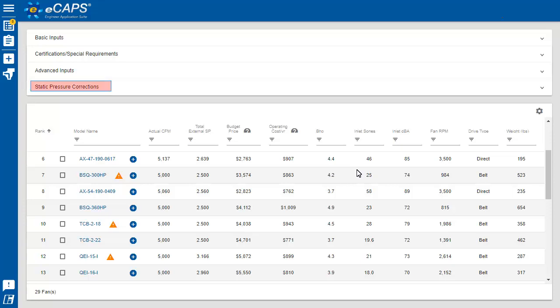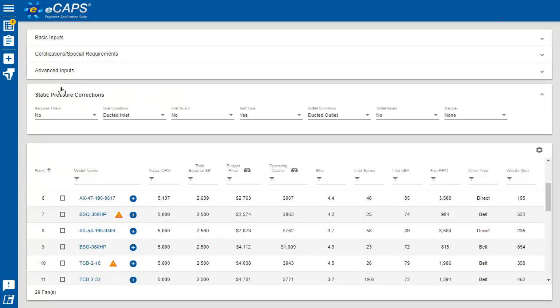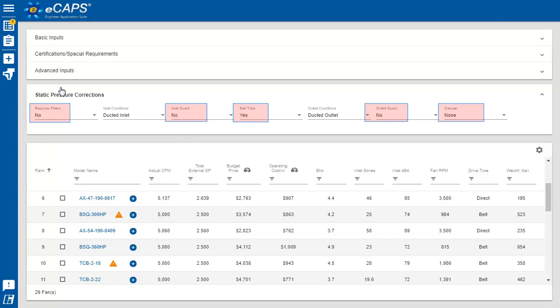To expand on the concept of keeping you out of trouble, we added performance corrections. Fan manufacturers offer fan accessories, many of which affect the fan's performance. Most fan manufacturers ignore their effects, resulting in poor test and balance results.